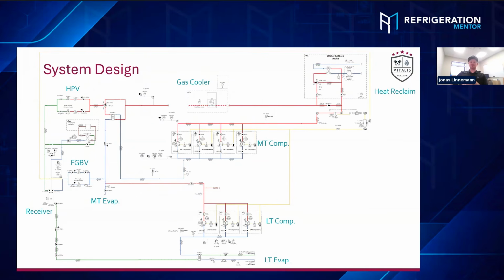So this is a very generic P&ID of one of our systems. We do have the medium compressor staging here, the discharge line, a heat reclaim, the gas cooler, high pressure valves expanding the CO2 from the high pressure side down into the liquid receiver. Then the liquid line is providing the low temp evaporators and the medium temp evaporators. It's one common liquid line. And the LT evaporators are connected to the low temp compressor suction, which is discharging back into the medium temp suction line, where also the flash gas is bypassed from the receiver into the suction line. Then an internal heat exchanger maintains the right suction temperature, and that goes right back into the medium temp compressors, right? So that's the typical design of a CO2 booster system.